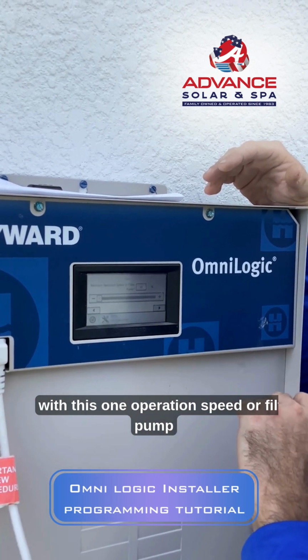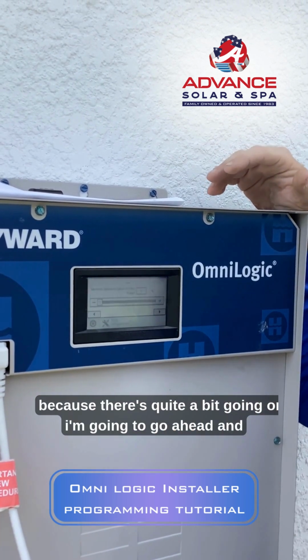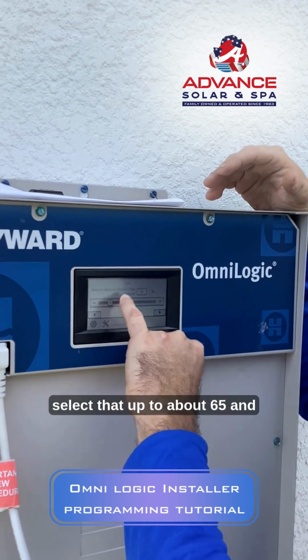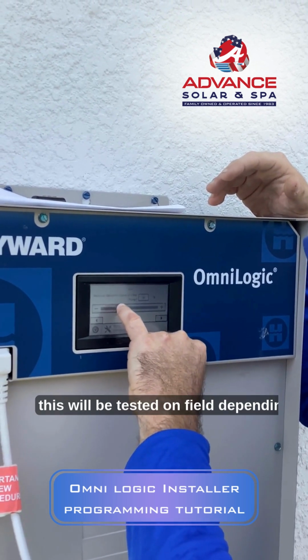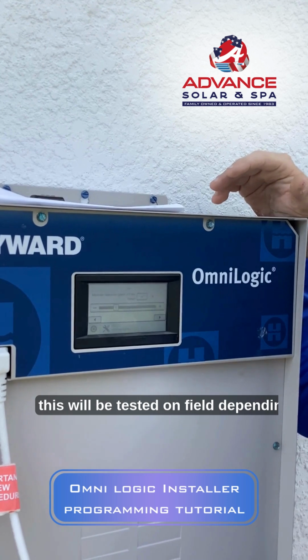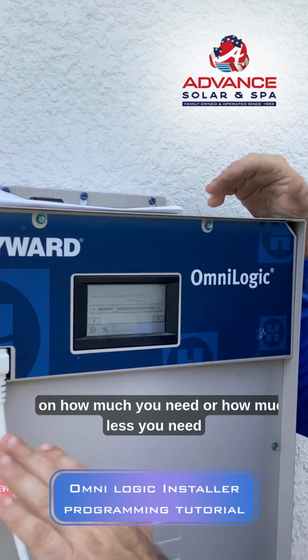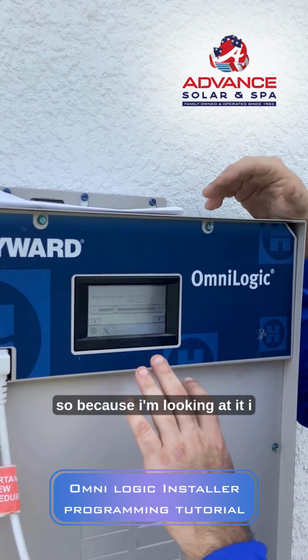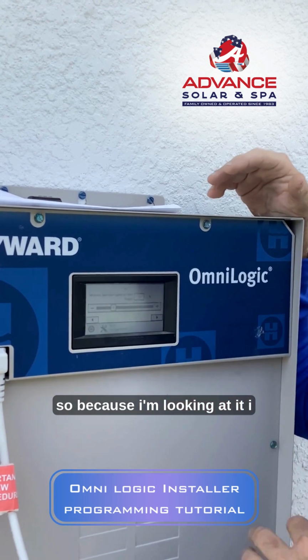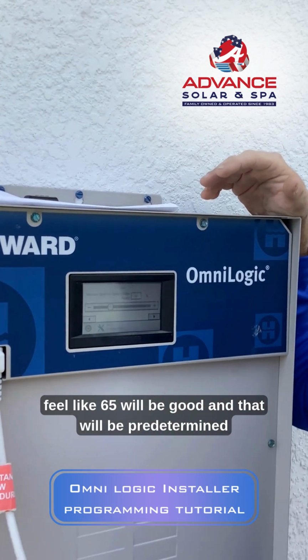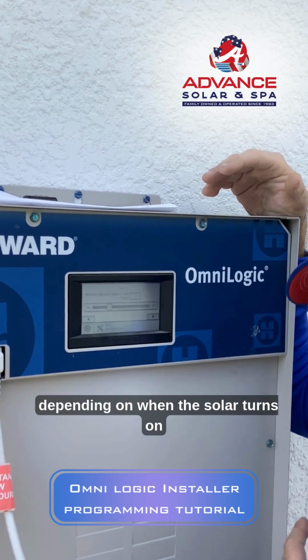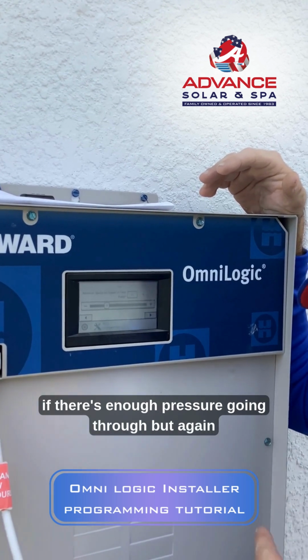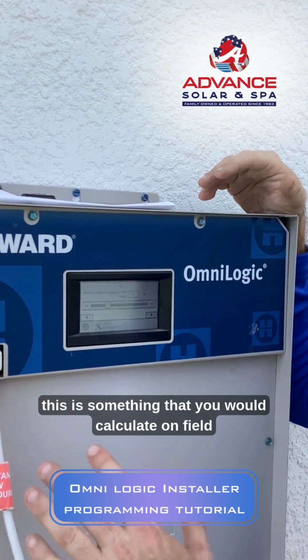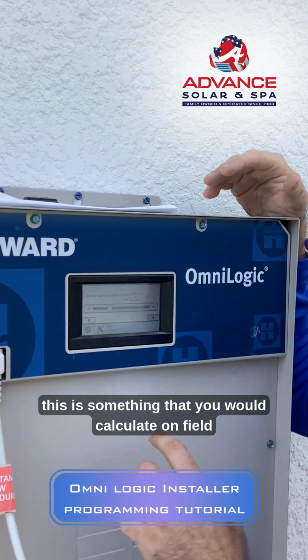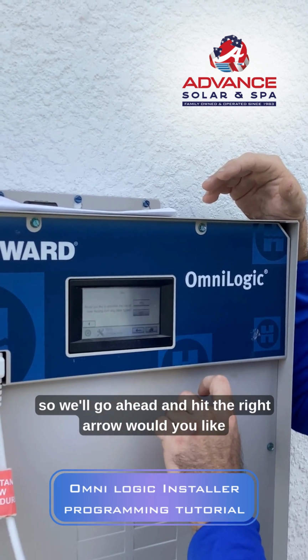With this one, operation speed for the filter pump, because there's quite a bit going on, I'm going to go ahead and select that up to about 65%. And this will be tested in the field depending on how much you need or how much less you need. Because I'm looking at it, I feel like 65 will be good, and that will be predetermined depending on when the solar turns on, if there's enough pressure going through. But again, this is something that you would calculate in the field. So we'll go ahead and hit that right arrow.